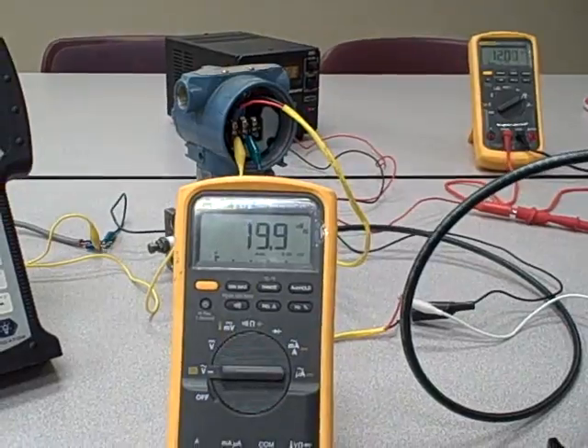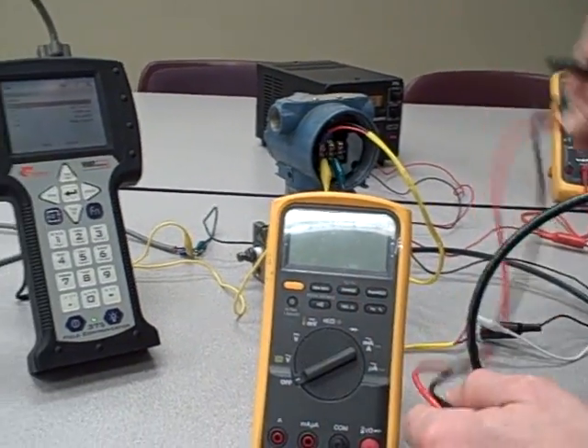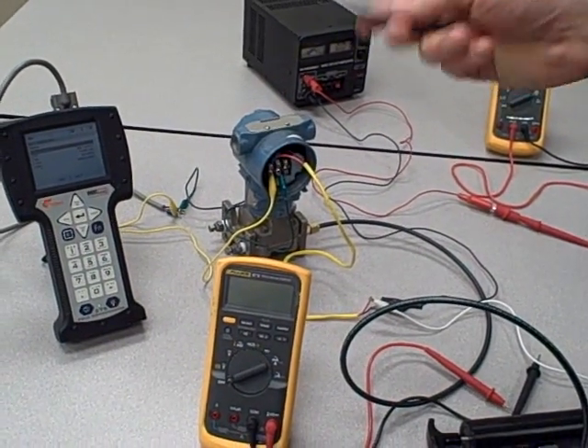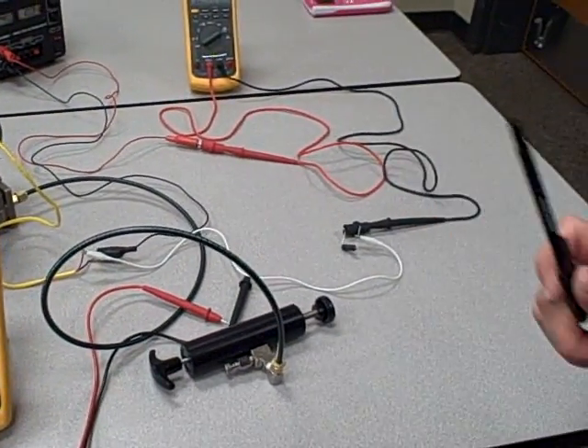That's a very easy detail to overlook, very easy to miss if you're setting up a transmitter on a test bench to do a HART communication activity with it. You need to ensure you have a loop resistance.